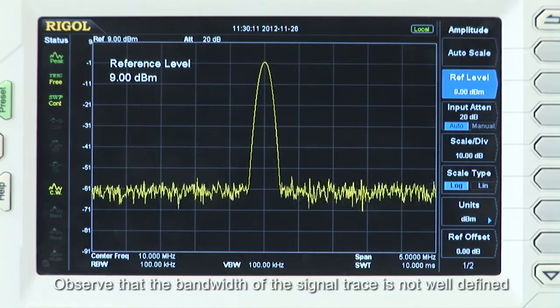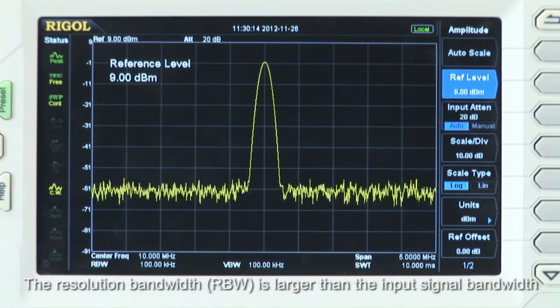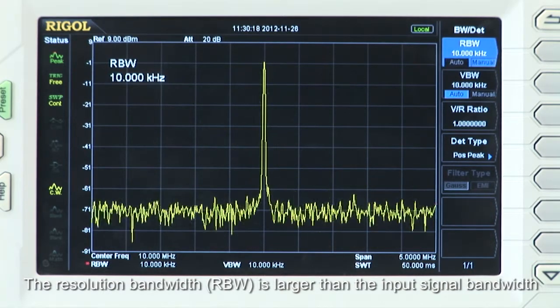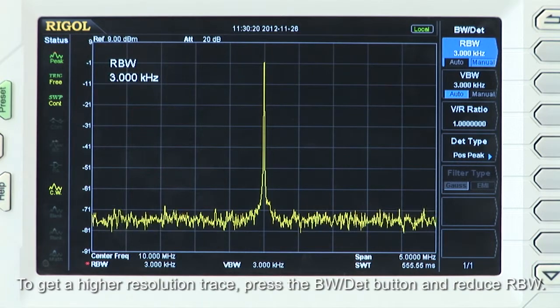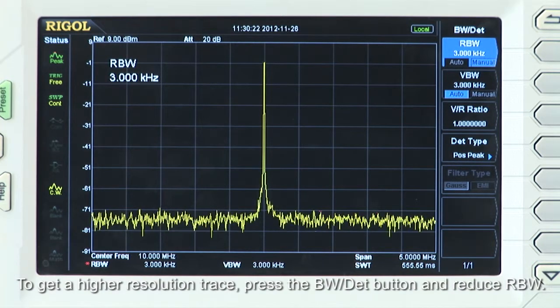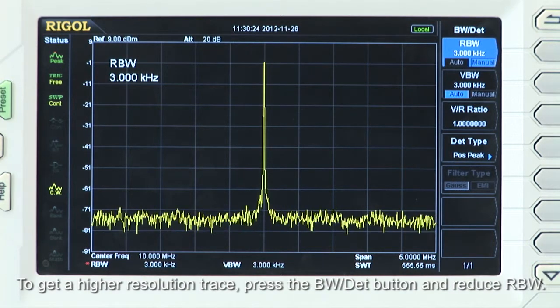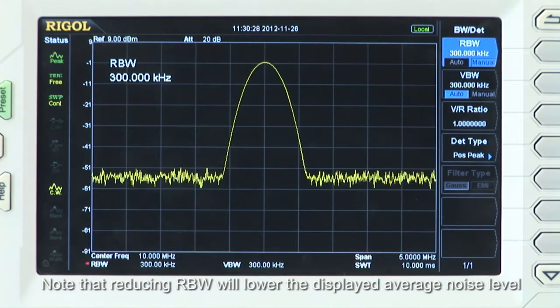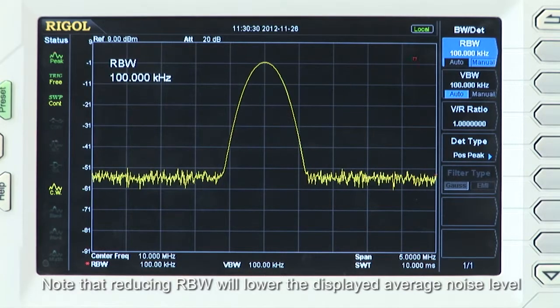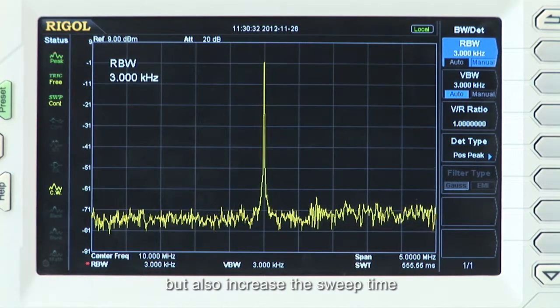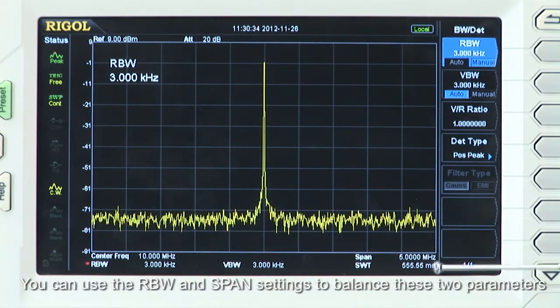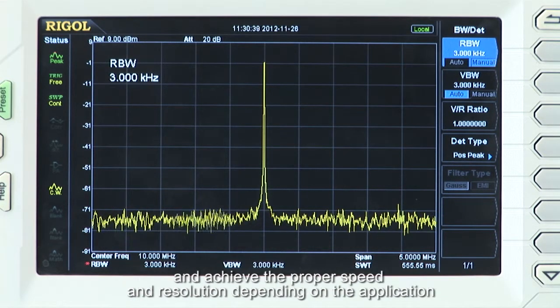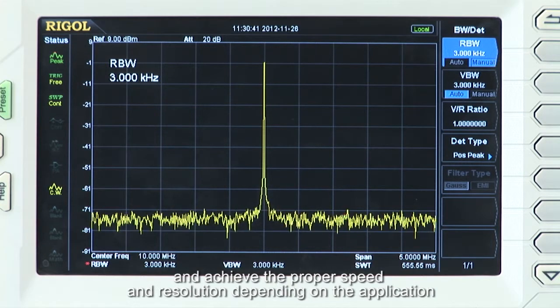Observe that the bandwidth of the signal trace is not well defined. The resolution bandwidth, or RBW, is larger than the input signal bandwidth. To get a higher resolution trace, press the bandwidth detector button and reduce the resolution bandwidth. Note that reducing the resolution bandwidth will lower the displayed average noise level, but also increase the sweep time. You can use the RBW and span settings to balance the two parameters and achieve the proper speed and resolution depending on your application.